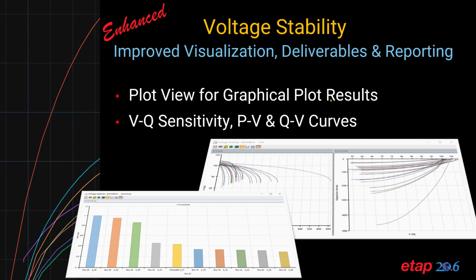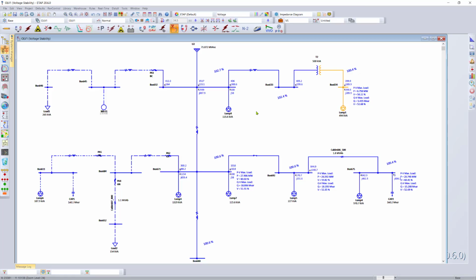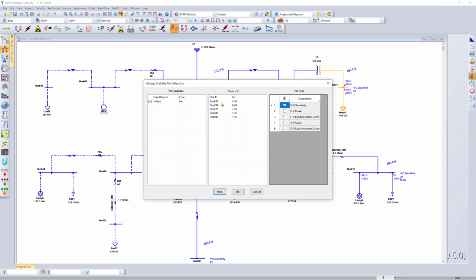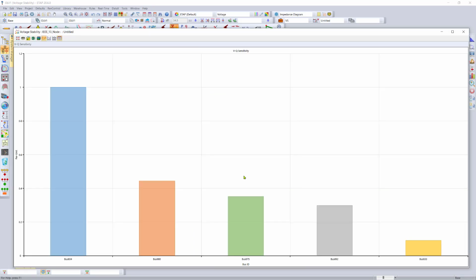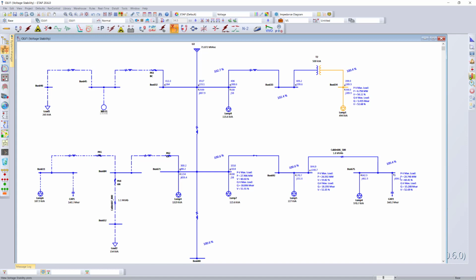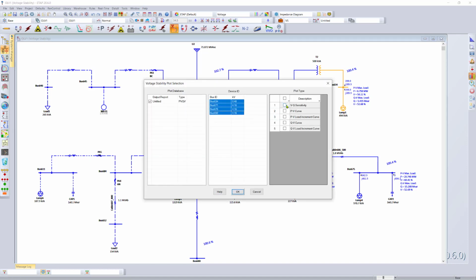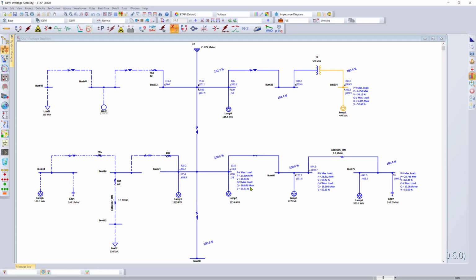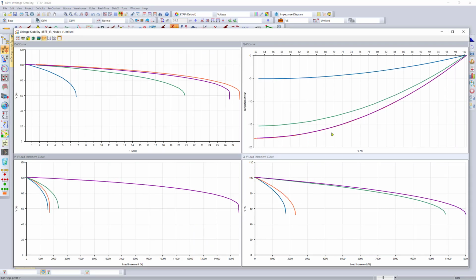The plot view now has graphical plot results for voltage stability that includes VQ sensitivity, PV, and QV curves. Simply go to an ETAP project, run the QV analysis, the sensitivity analysis, open up the plot view to essentially see the results of the sensitivity analysis across all the different buses. You can also run the PV and QV analysis across the entire system and see the QV and PV curves on the plot views at the same time.